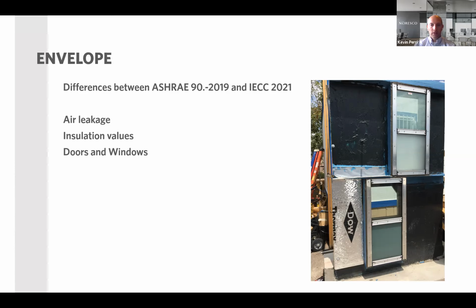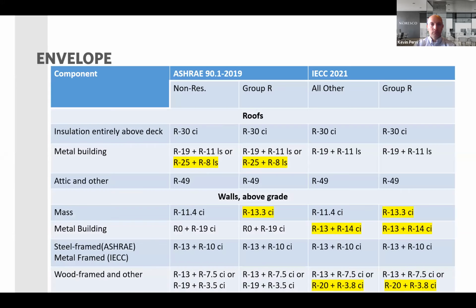So doors and window U-factors, we're using... let's jump into insulation values first, sorry. So I've created this chart. You can see the components on the left, then we have the categories of ASHRAE 90.1 2019, non-res, and then group R, and then you have IECC 2021, group R, and all other. I try to make it easy for you: anything highlighted in yellow is different from the others. So quite a few similarities, probably more similarities than there are differences between the two pathways of ASHRAE and IECC in terms of insulation values.